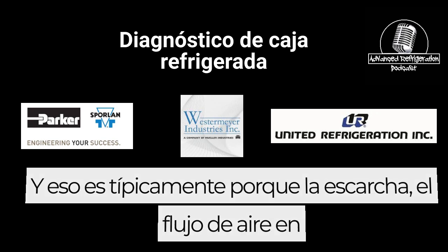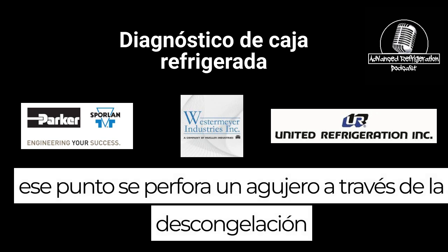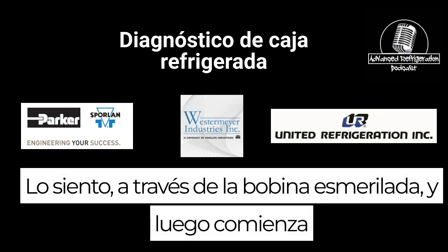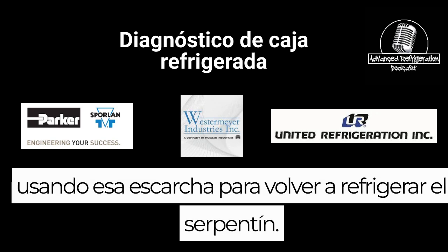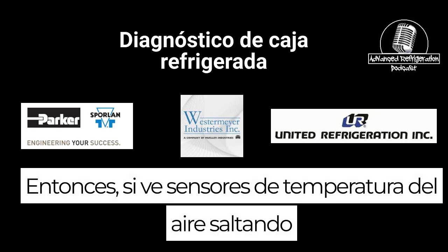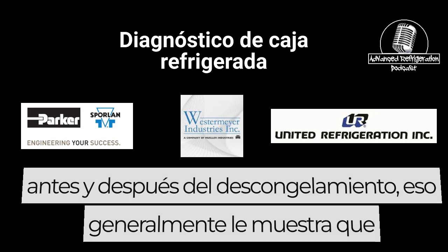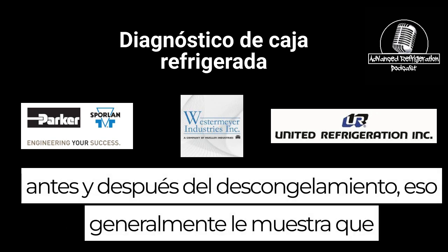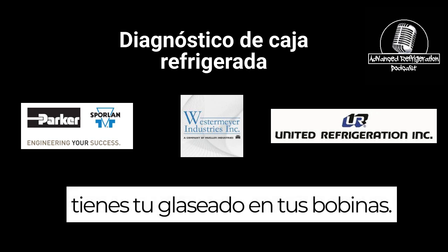and then back up. That's typically because the airflow at that point has punched a hole through the frosted coil, and then starts using that frost to re-refrigerate the coil. So if you see jumping around in air temperature sensors before and after defrost, that's typically showing you that you have frosting on your coils.